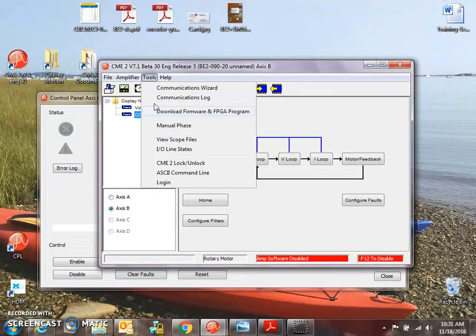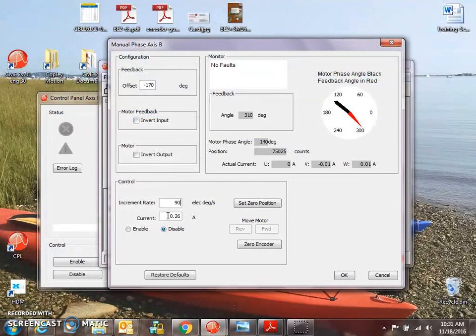Tools, Manual Phase. Let's give it an amp. Forward. Reverse — oh, that's backwards. Let's invert the feedback. Set zero, move forward, counts go up. So there's a little offset here: minus 170. Forward and reverse matching exactly.